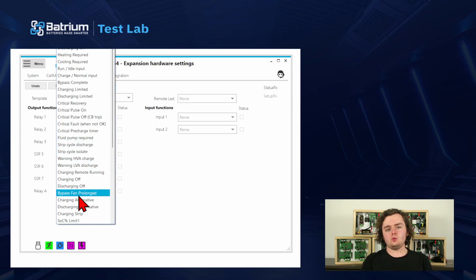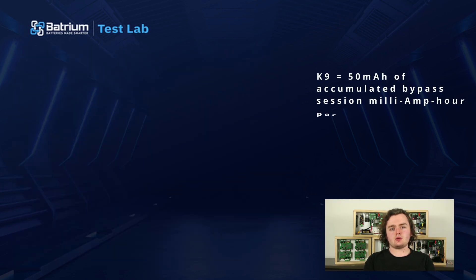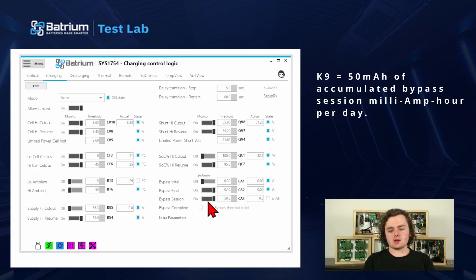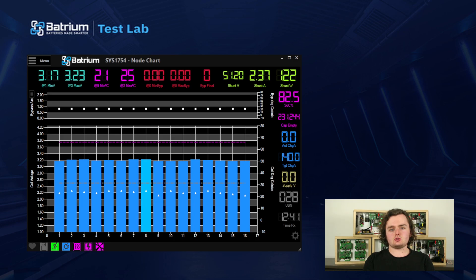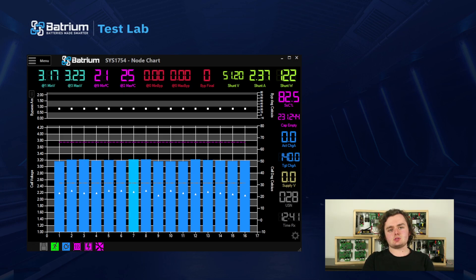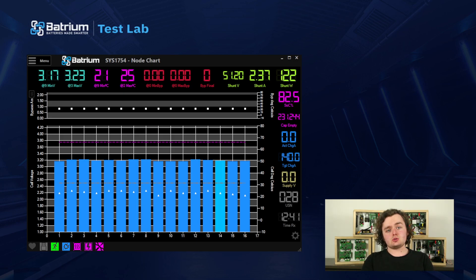The battery pack is declared full when all cells have reached 50 milliamp-hours of accumulated bypass session milliamp-hours per day for k9s — you can see that here under bypass session, waiting for 50 mAh on all cells to declare the charge complete. If you're using block mons instead, all of them need to have bypassed at least 100 milliamps before the charge is declared done. When this happens, the BMS declares the pack full and resets the state of charge to 100% to avoid state-of-charge drift, which is really important because small inaccuracies add up over time.